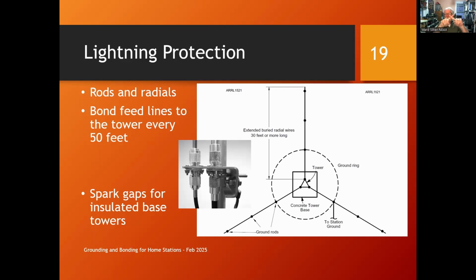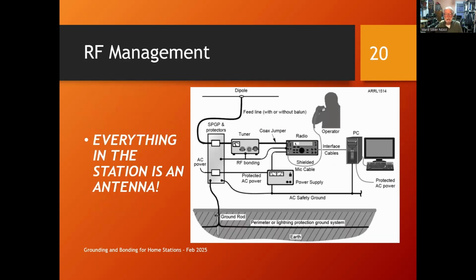The reason I do it this way and not this way is that when the wires cross at an angle, the rain does not accumulate in that gap. Insects don't build nests in there, and that would cause a short if there was a lightning strike. The lightning comes along, it builds up the voltage, it arcs over between those wires, and it discharges the tower into your ground system. So that's a way to protect an insulated base tower.